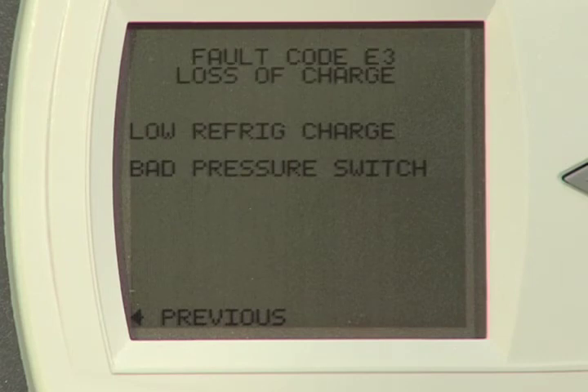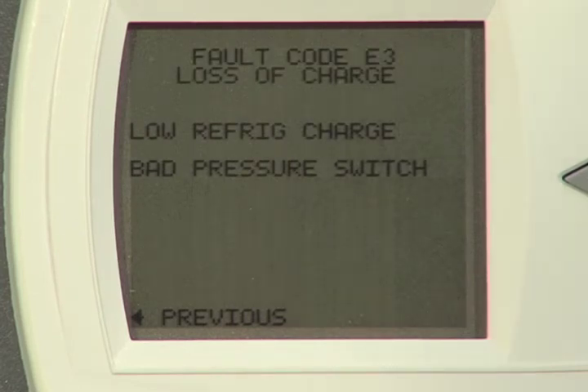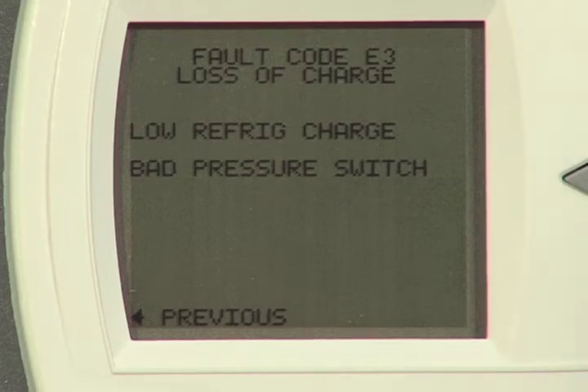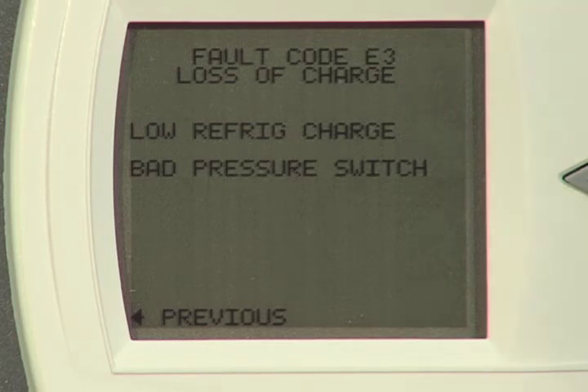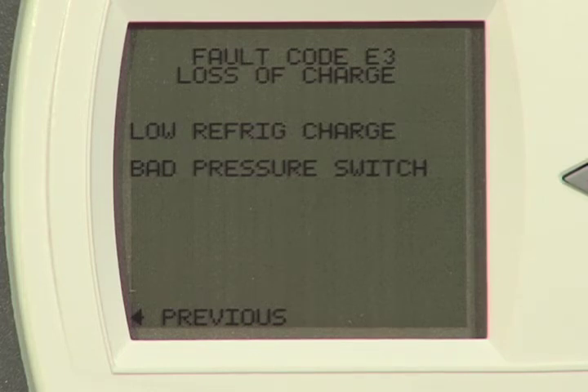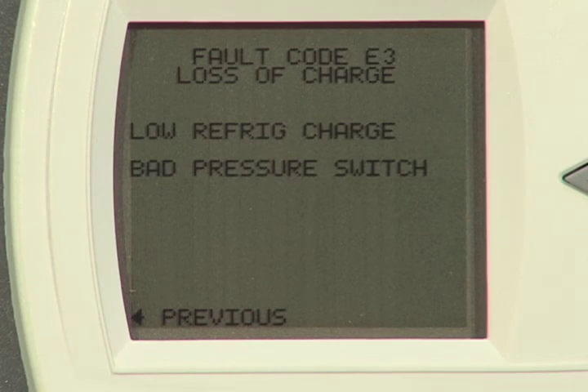We'll choose that fault, and a couple items come up. First thing is low refrigerant charge or possibly a bad switch. Probably the first thing we want to do is, once the system has shut down and equalized the pressure, we want to verify if that switch has now closed — we can do that with our voltmeter. Then, if that has closed and we're still having an issue, we're going to need to get out our refrigerant gauges and verify the charge on this system.